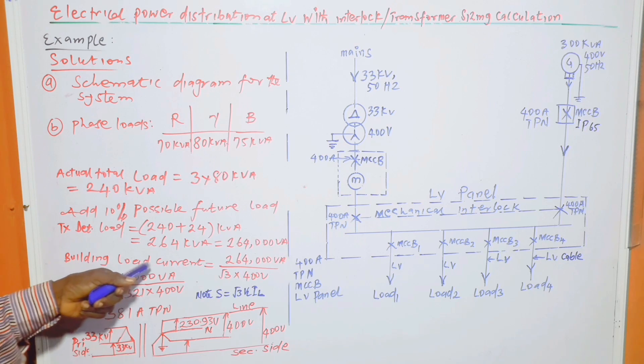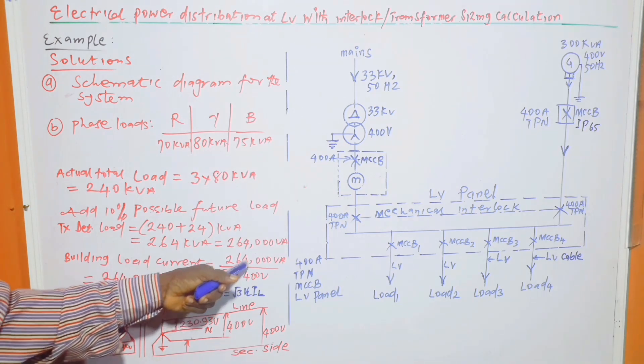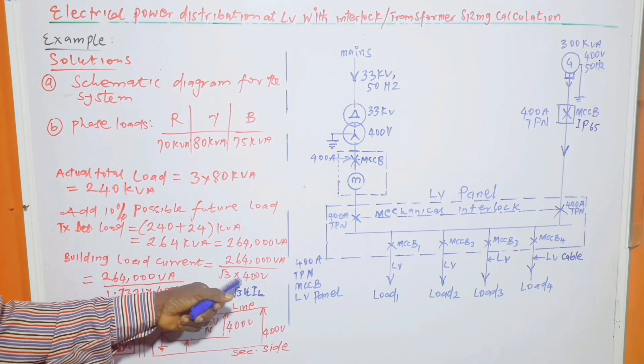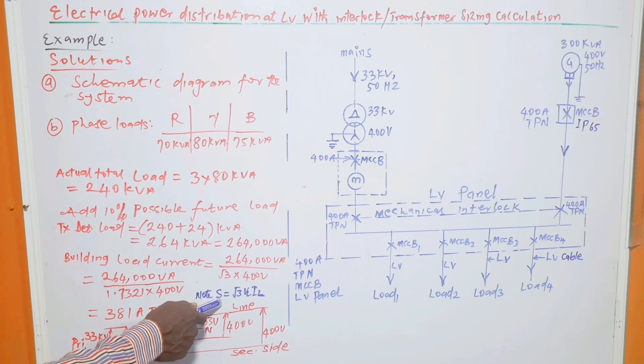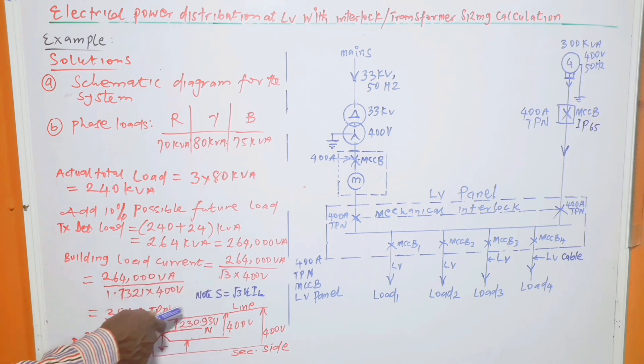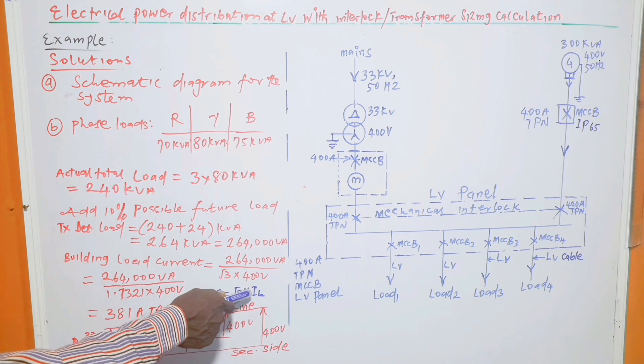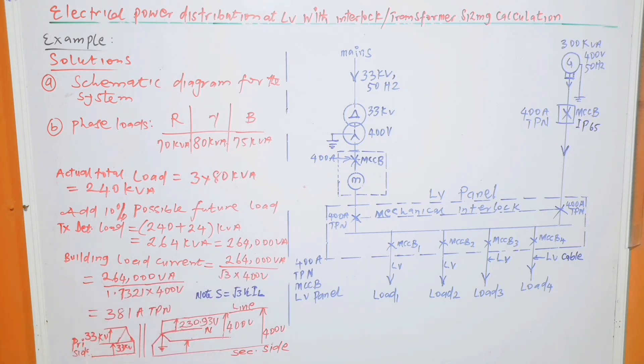Then we can move further to calculate the building load current, which is equal to 264,000 VA divided by root 3 times 400 volts. So from this formula S equals root 3 times V line times I line, from which we can calculate I line to be equal to 381 ampere triple phase with neutral. In this case, it doesn't mean that the neutral current is 381. We are just saying that we have three phases plus neutral. It is the line current, which is equal to the phase current in this situation, that is 381 ampere.